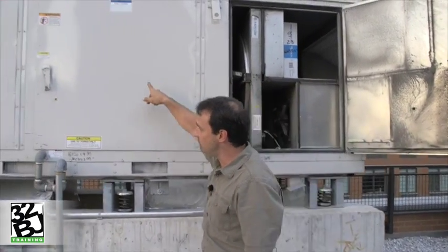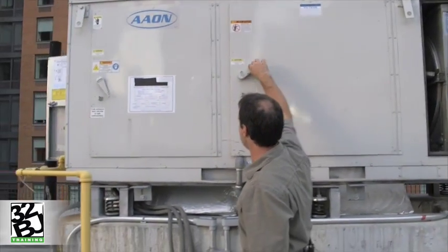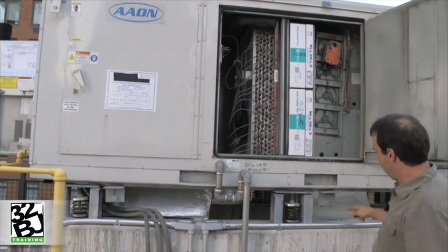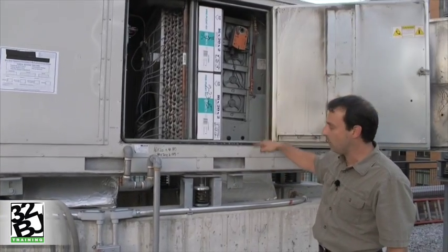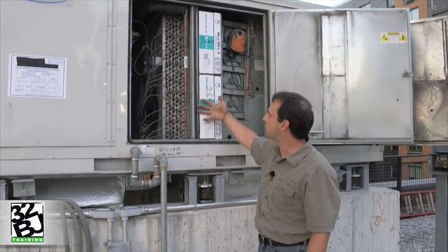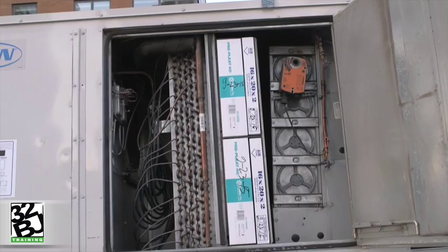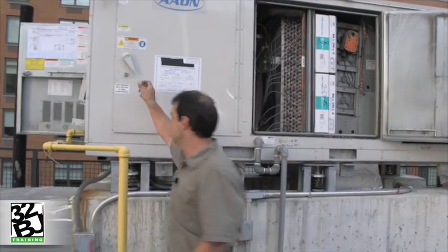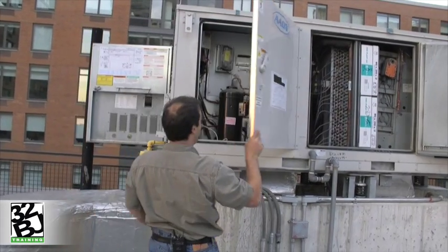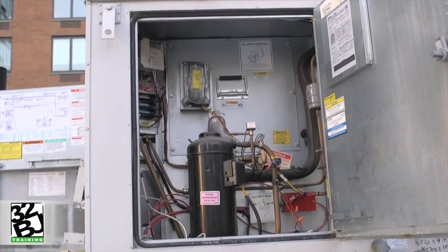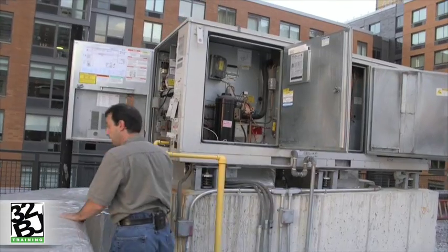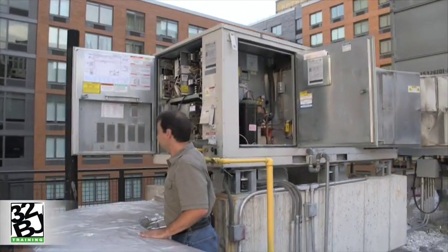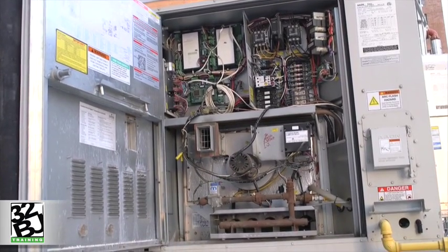The fresh air continues being dragged by the fan, where it mixes with some return air from the hallway and passes through the main filter bank. That air is then either pre-cooled by our air conditioning coil and our compressor, or if the air is too cold, it can be preheated through the gas-fired heating furnace. Let's take a closer look at that enthalpy wheel.